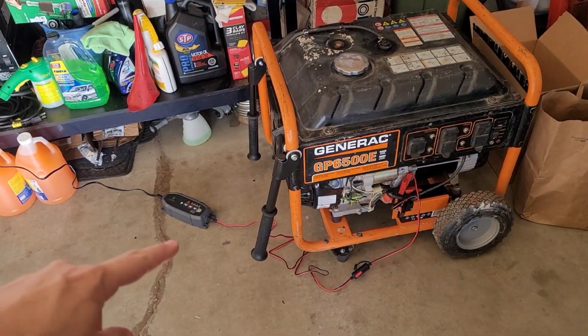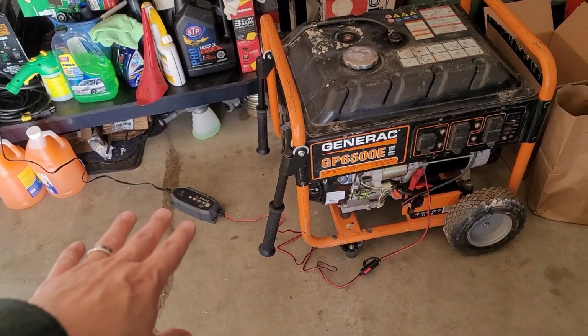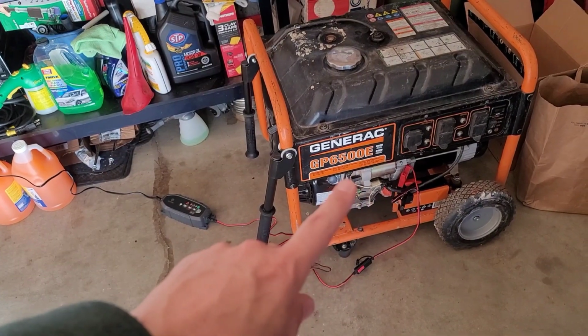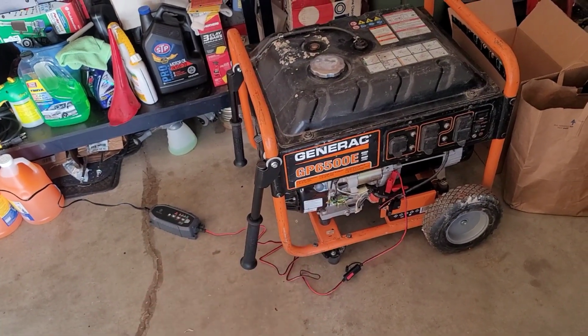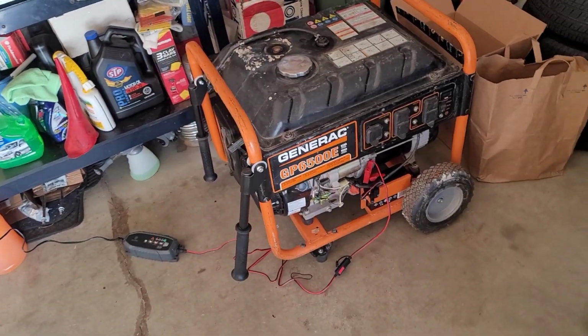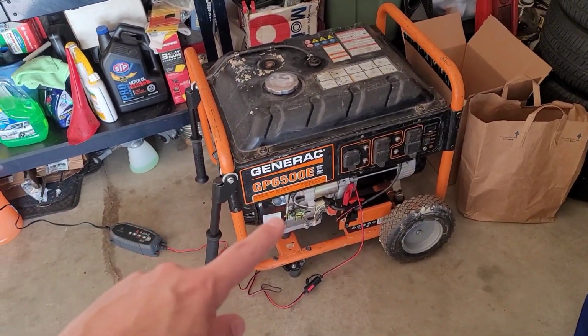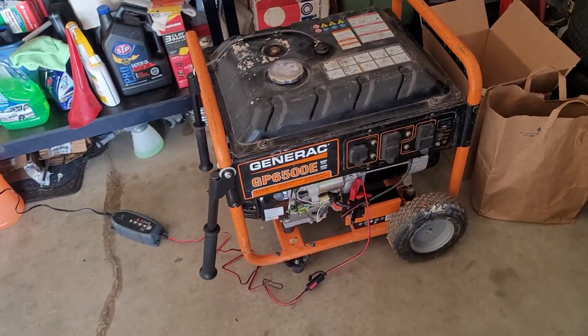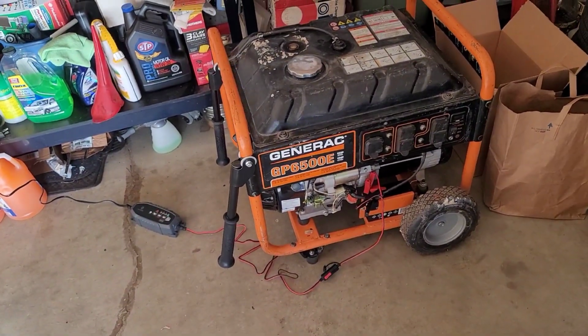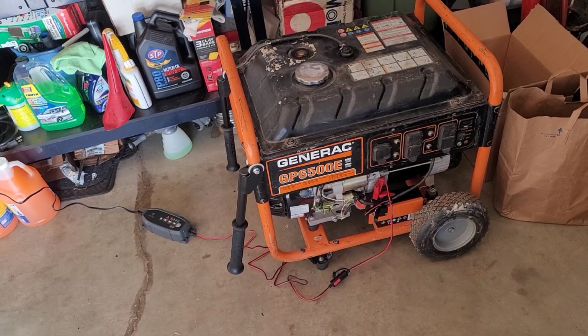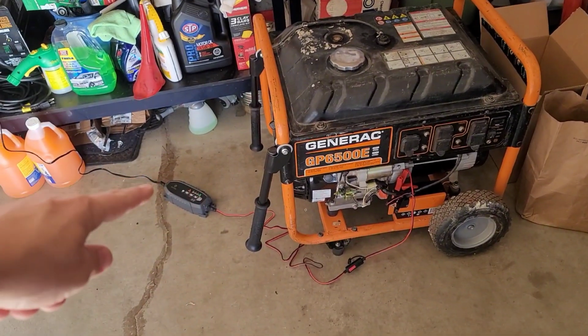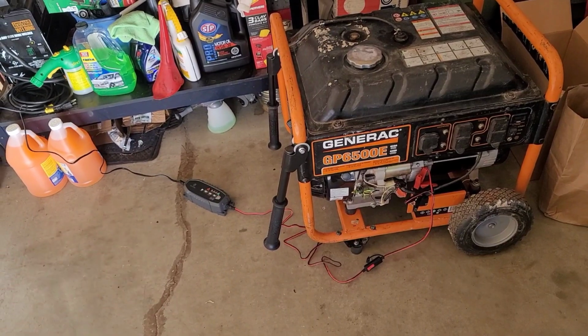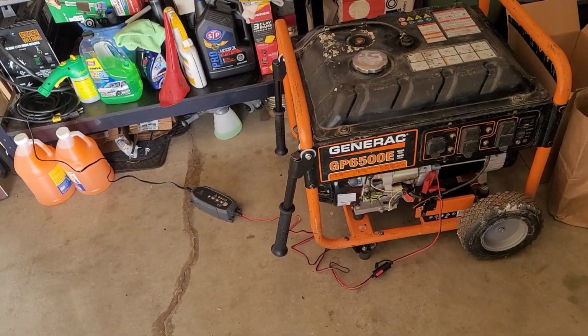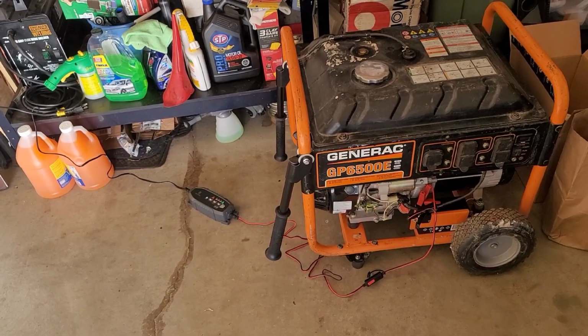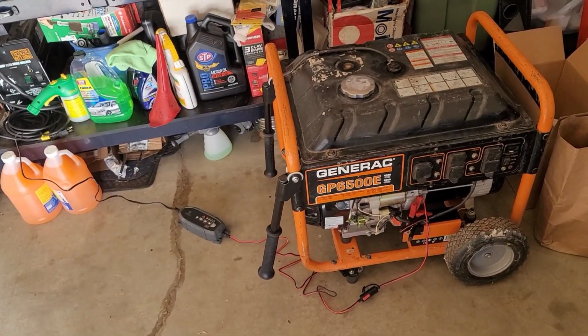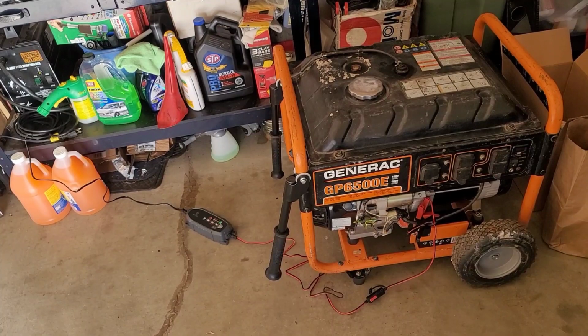I'm going to go ahead and charge the battery here with an external multi-stage smart charger. This generator, unfortunately, the GP series in general, with the exception of the 15,000 and 17,000 watt, I believe, does not charge the onboard starter battery. That's why they give you the DC port in the front. There is a wall wart that you can buy to basically charge it, but they don't want you running it for more than 48 hours. This I can leave on there indefinitely because once it's charged, it'll go to a float mode and not overcharge that battery. But it's good to do to make sure that the battery doesn't go flat, and you'll be ready to crank the engine when you need it.